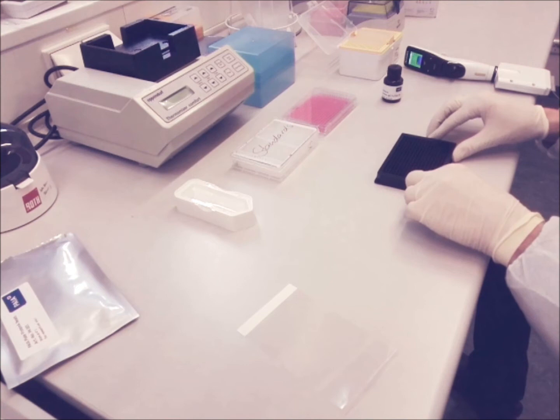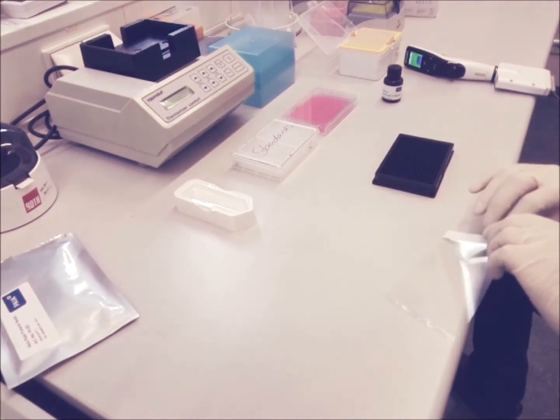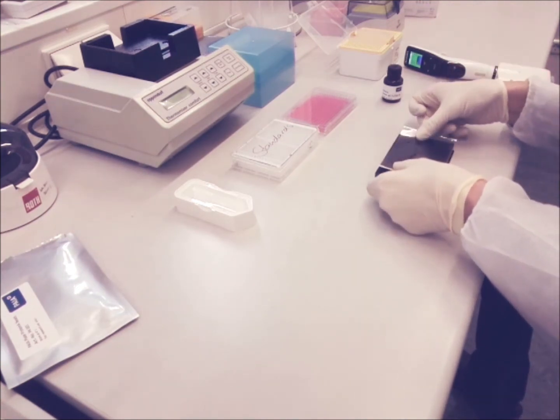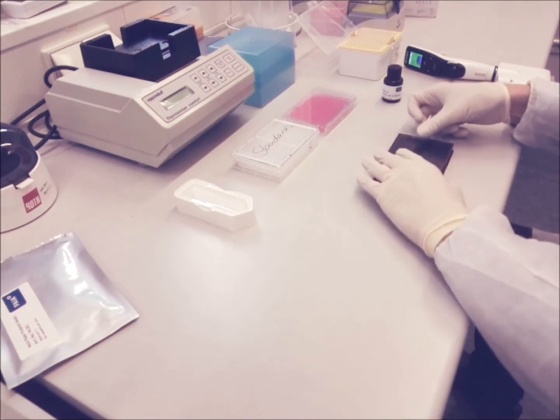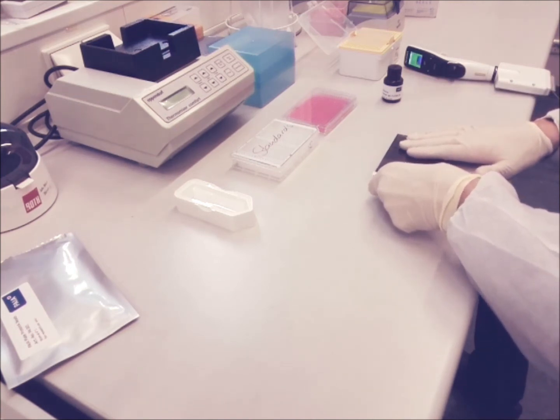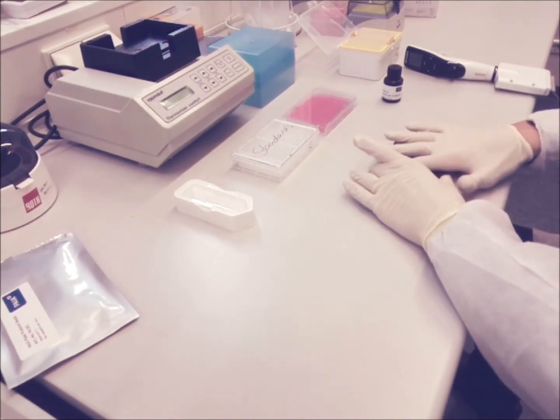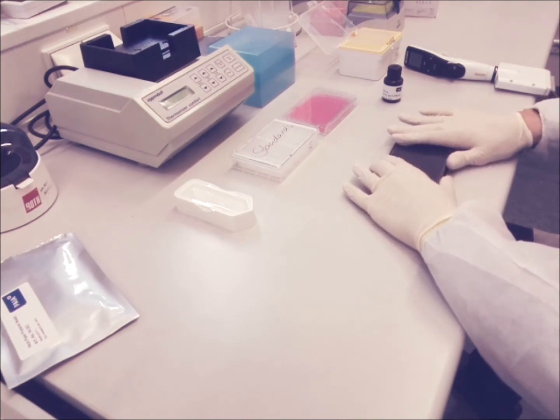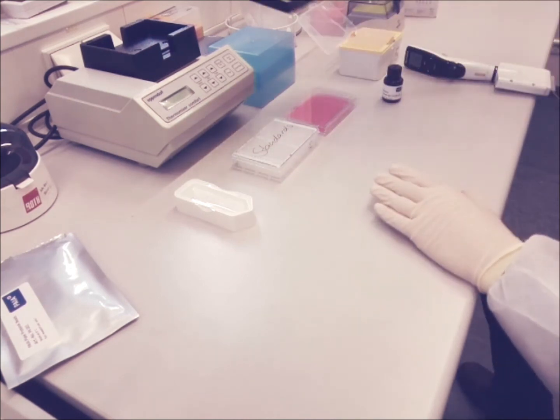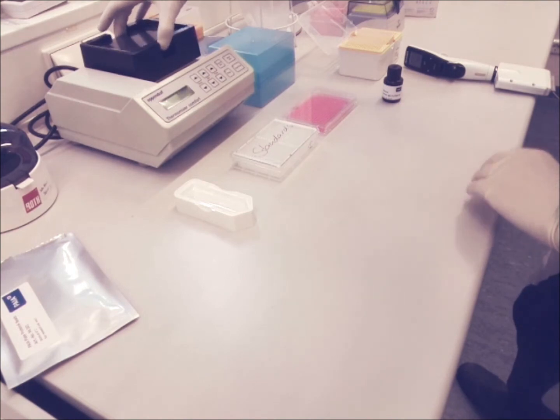Now the plate is ready to incubate. You may seal the plate prior to incubation, but this is not necessary if you have checked that the samples do not spill over during incubation. It is important that the shaking is efficient. Depending on the shaker model, the shaking speed should be set between 1400 and 1800 RPM.